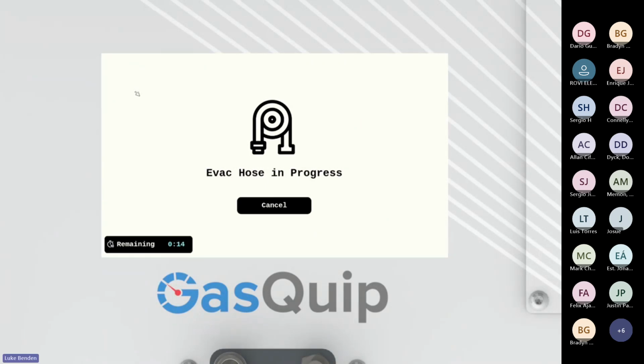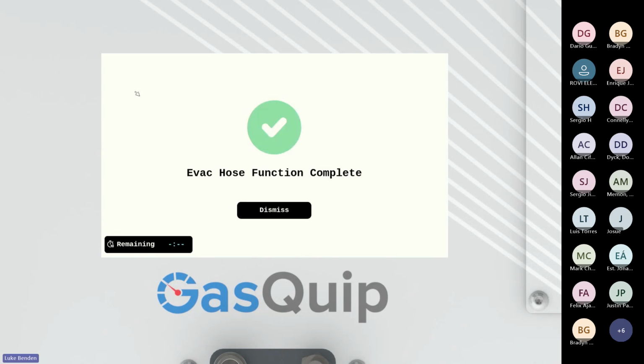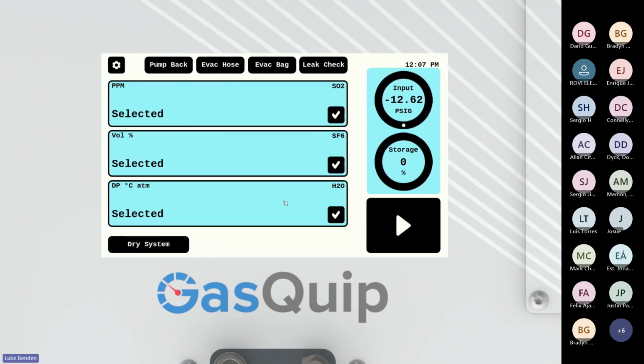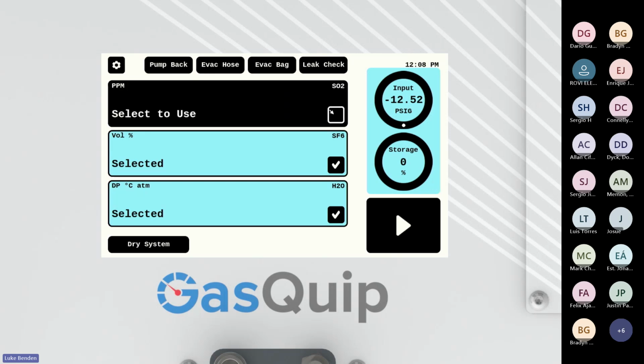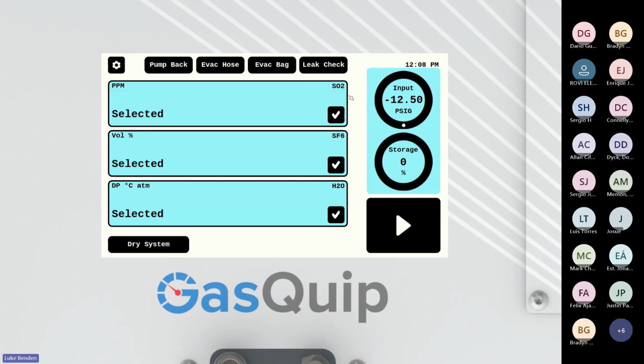You can hear that vacuum pump kick on, and then we'll get a confirmation that the hose has been evacuated. We can also verify that if we click dismiss. Here in the input pressure, we now see a negative 12 PSI showing for the input pressure, telling us that we have evacuated our hose. So we can select and deselect the sensor modules that we want to test from. So we'll just leave those connected.